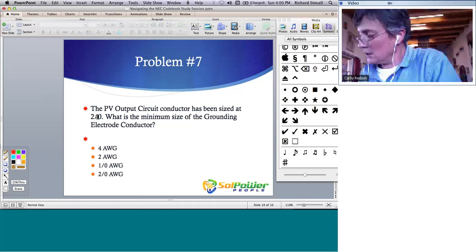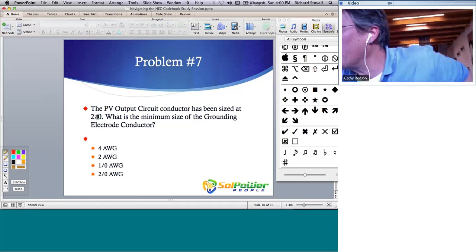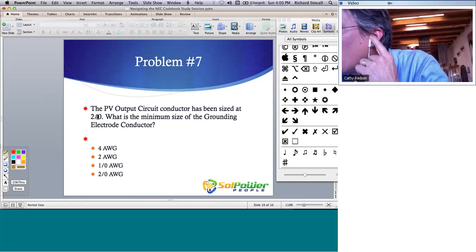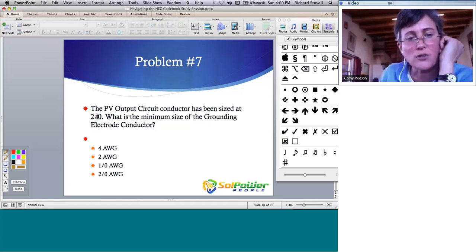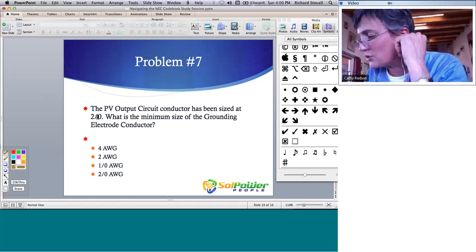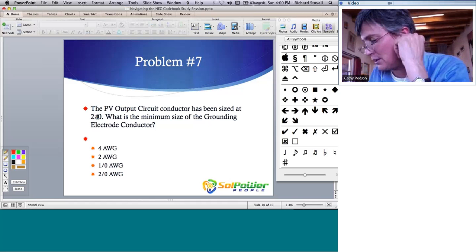Wait a second. I'm going to look at the right table. Hold on. I want the one for grounding electrode conductors. Yeah, hold on, 250. What's that? 250.66. That's where I should be. Excuse me. Okay, 250.66, thank you so much. That's the chart I was looking at. So the grounding electrode conductor, not the equipment grounding conductor. So there you have it. It's that easy to put yourself into the wrong section of the code book. So in the Mike Holt book, this question would be explained more fully on page 82, where you have table 250.66.